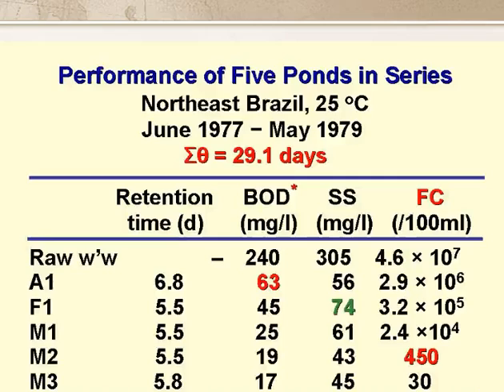This slide shows the performance of a series of five ponds in northeast Brazil in the late 1970s. The anaerobic pond had a retention time of nearly a week — much too long — and the facultative and three maturation ponds had retention times of about five and a half days. Most of the BOD and suspended solids were removed in the anaerobic pond as expected, and suspended solids actually increased in the facultative pond due to algae growth. The truly remarkable performance was the removal of faecal coliform bacteria — more or less by an order of magnitude in each pond — down to 30 per 100 ml in the final effluent, a better bacteriological quality than the water most people in developing countries have to drink.